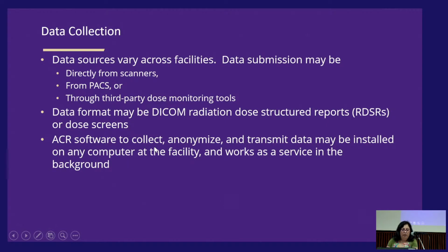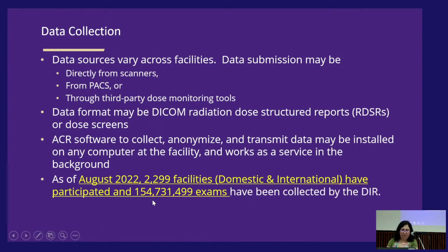The software will collect, anonymize, and transmit data, and it's installed on any computer at your facility, and it works as a service in the background. So once you set it up, you could say forget about it, but in my experience, you can't say forget about it, because sometimes the data will stop transmitting to ACR, and then you have to figure out what happened. So you kind of have to keep an eye on it with your IT person, or you as a physicist have to keep an eye on it.